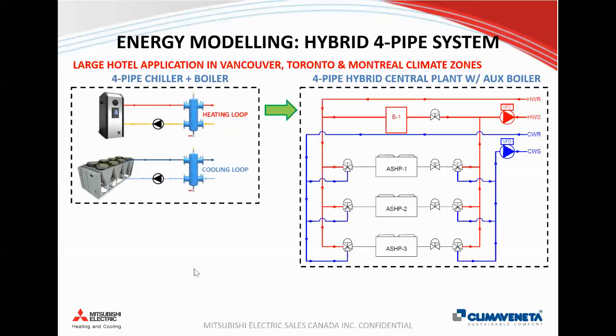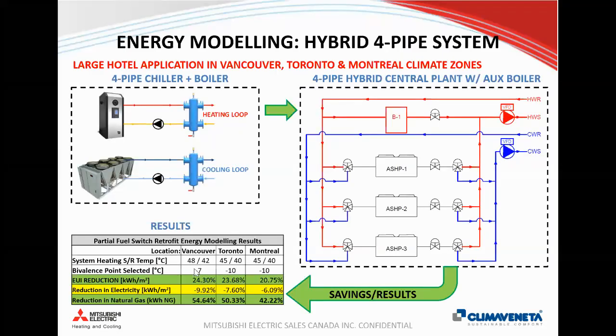One example that we've done for energy modeling is we looked at an older building that had a chiller boiler system and asked, how do heat pumps fit into this building? So we analyzed a large hotel in Vancouver, Montreal, and Toronto with the same system in all those buildings, basically replacing natural gas as much as possible. In those examples, the heat pumps were sized to operate in Toronto and Montreal down to minus 10 with a 45-degree-Celsius supply. In Vancouver, the design temperature was minus 7, so that was with a 48-degree supply, according to the operating limits.